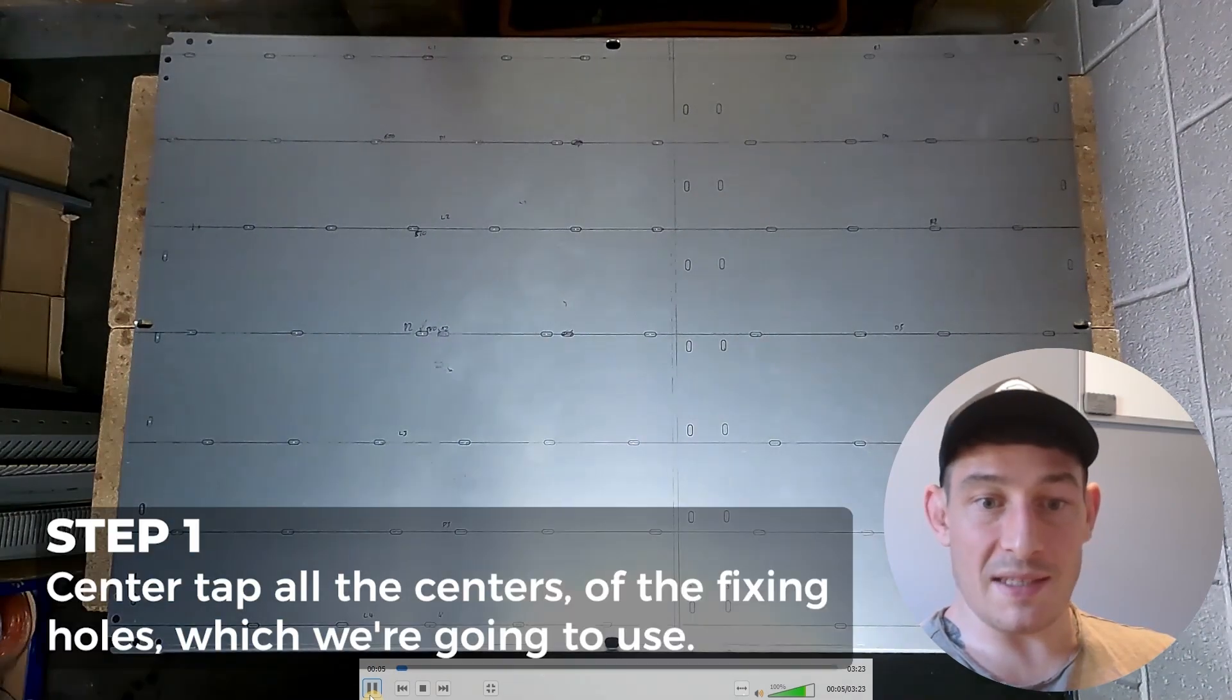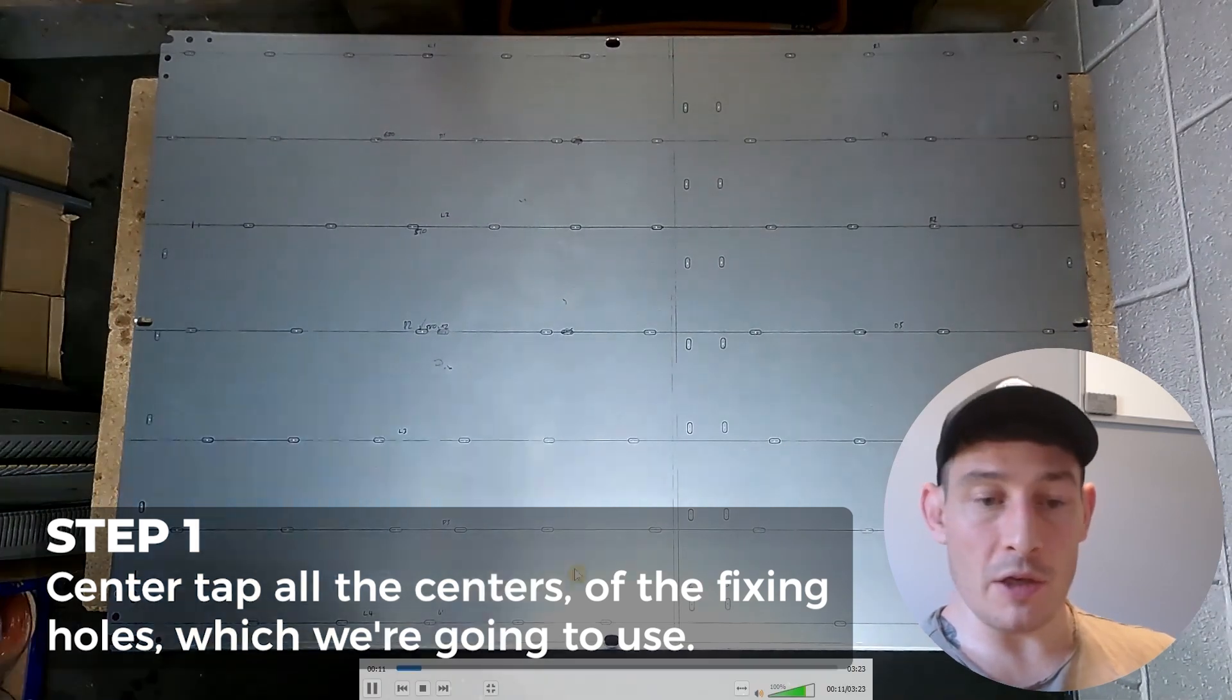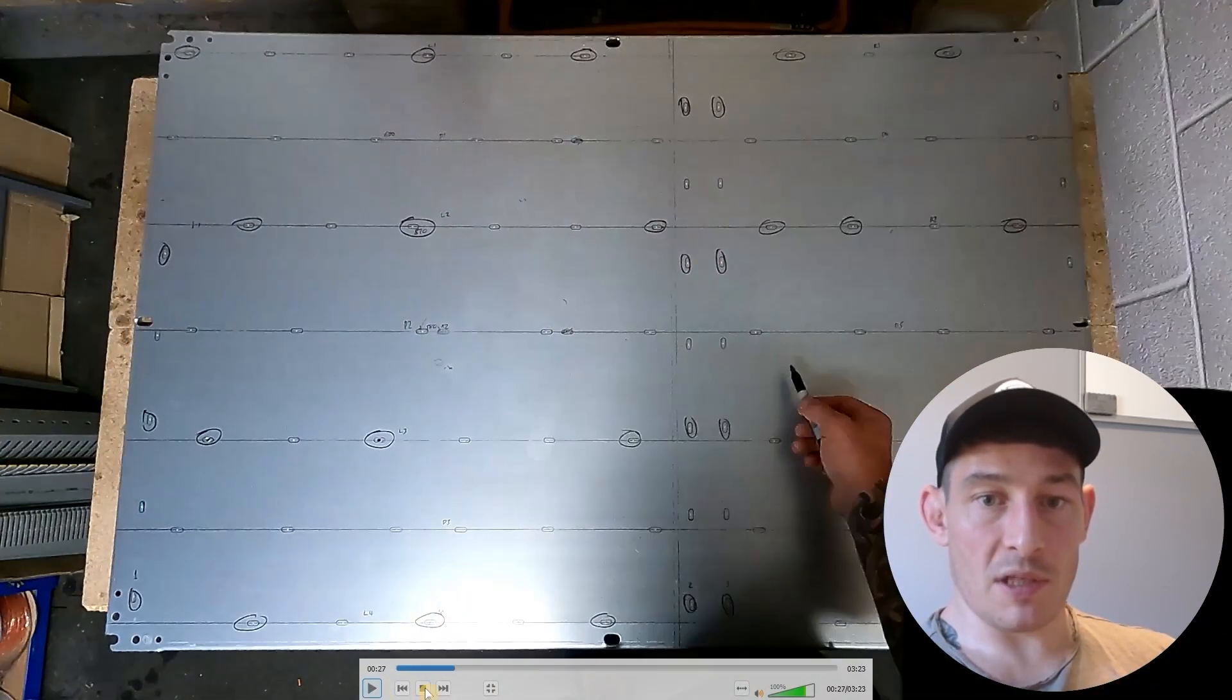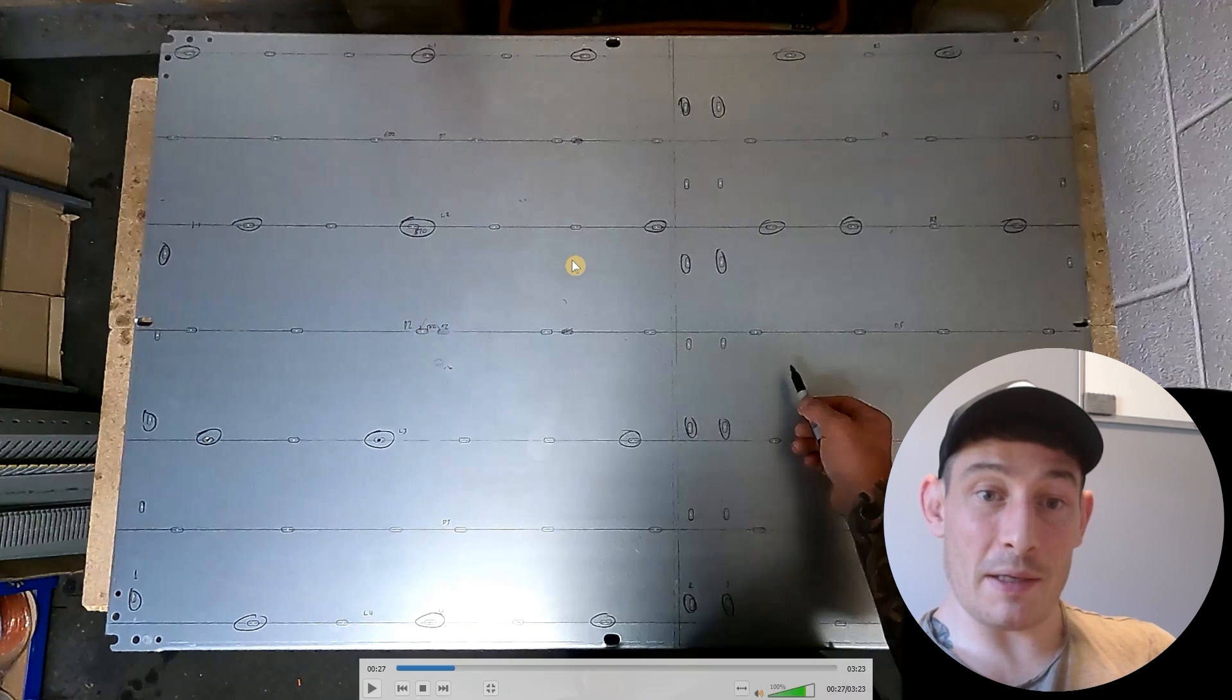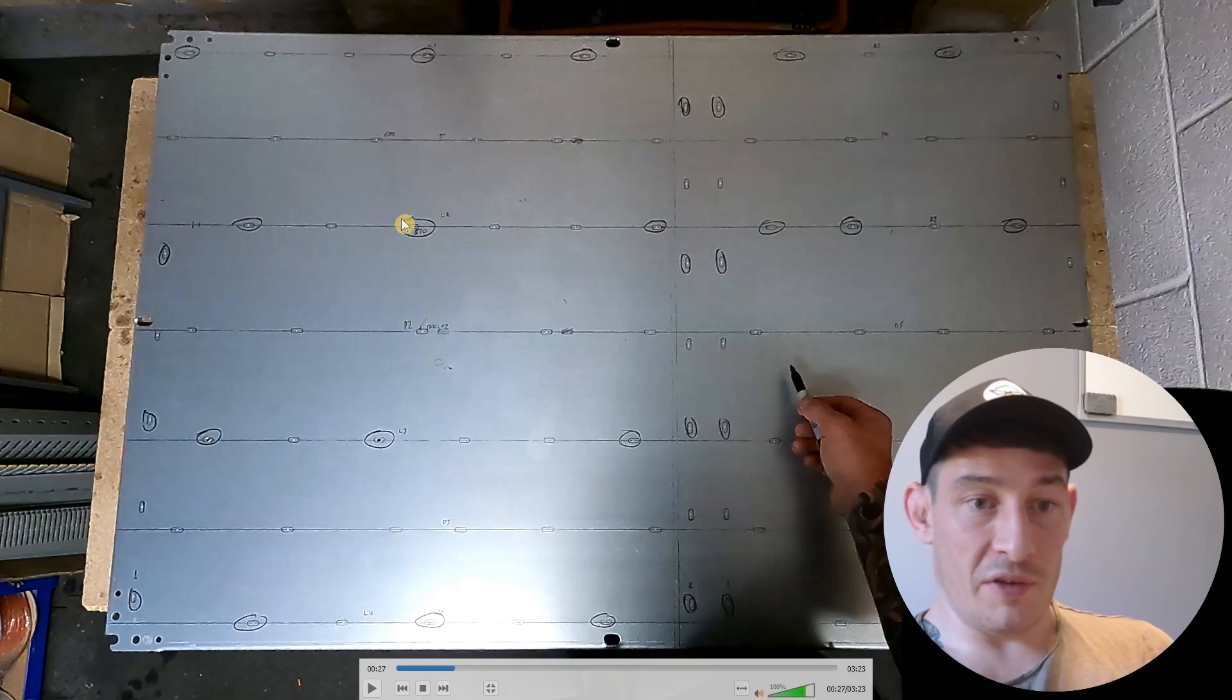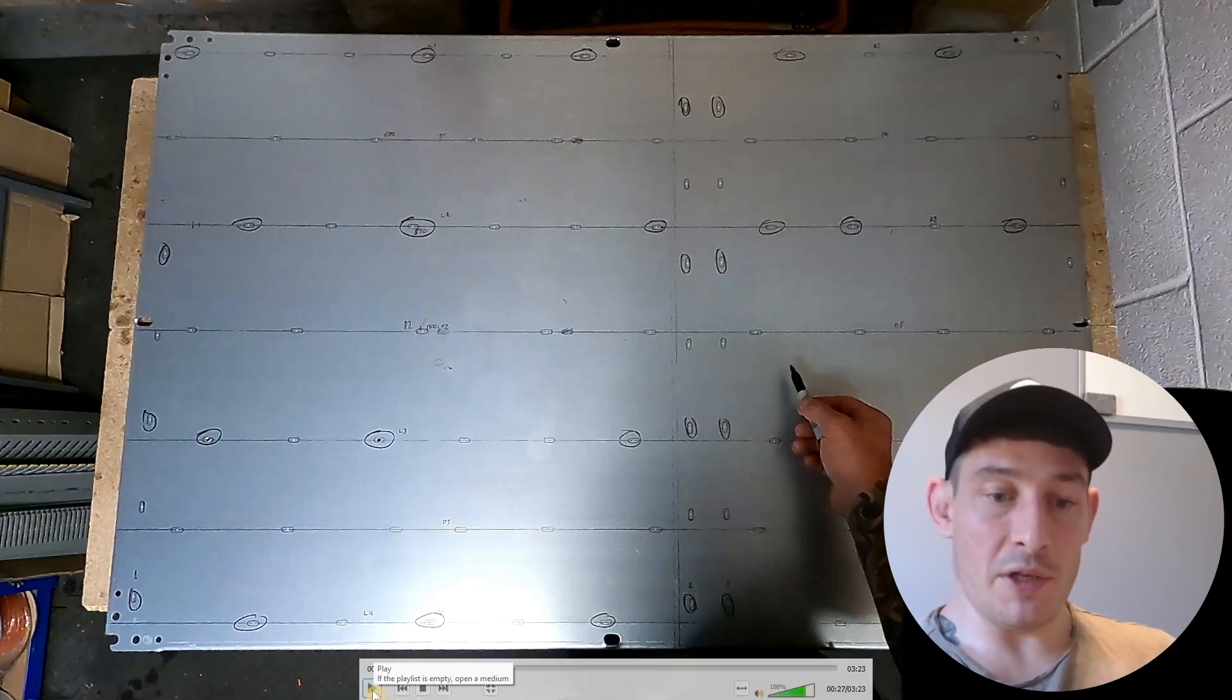So first things first is center tapping all the centers of the fixing holes which we're going to use, and then as you'll see here I'm circling all of the fixing points which I'm going to drill. So we could have done this before doing the center tapping. Ultimately we don't need to use every single fixing hole, it's just complete overkill. So as you can see I'm skipping one or two, having fixings each end of the trunking and then one in the middle. That's typically how I do it.